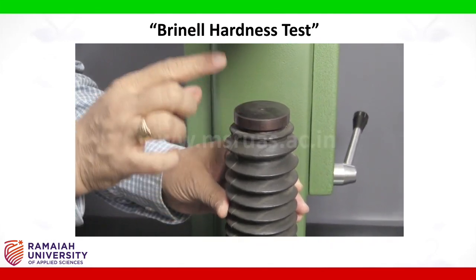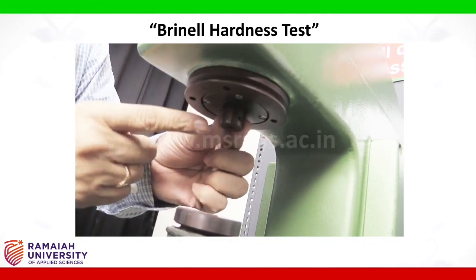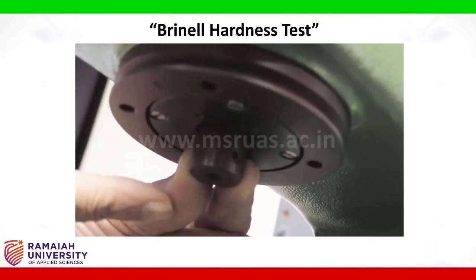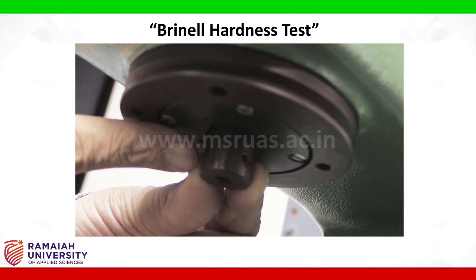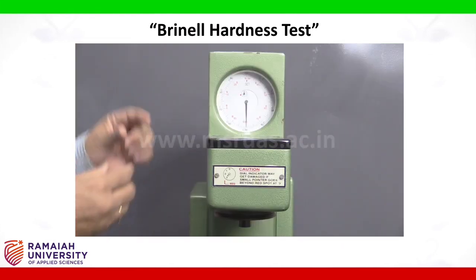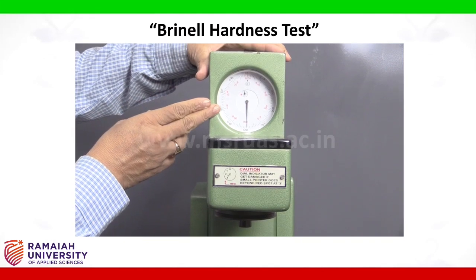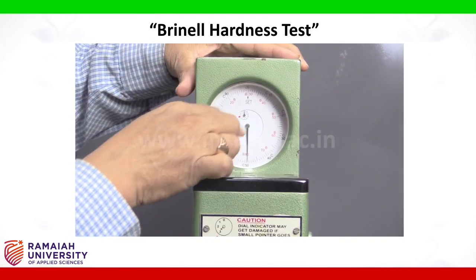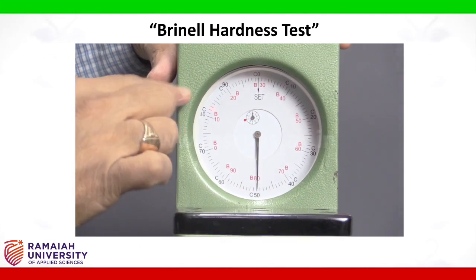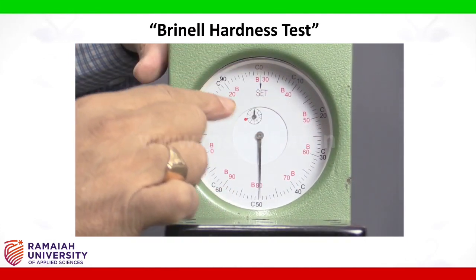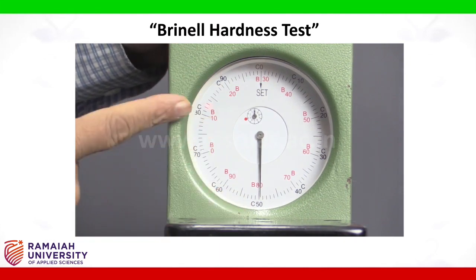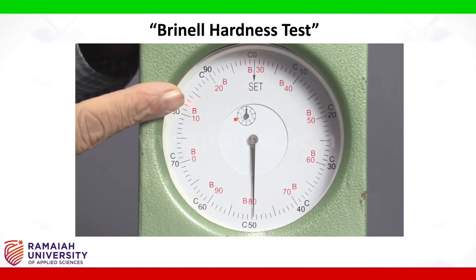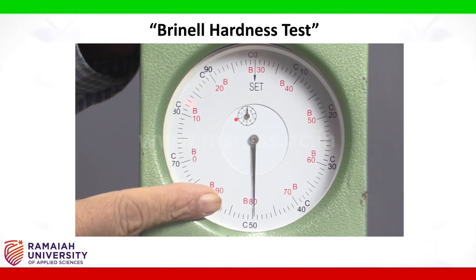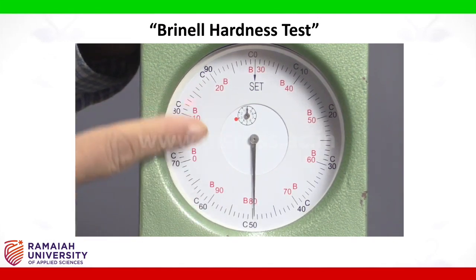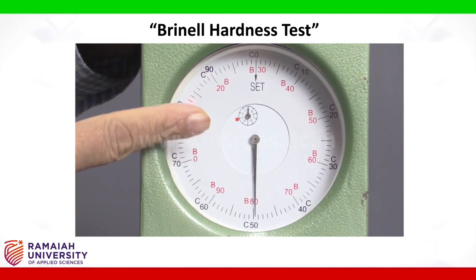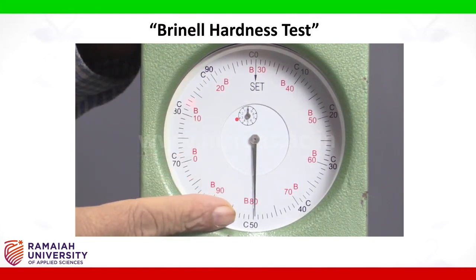On the working table we keep the specimen. The machine consists of the main shaft to which the indenter is fixed with the help of the Allen key. Next is the dial gauge. The dial gauge consists of an outer scale and an inner scale. The outer scale is the black C scale and the inner scale is the red B scale. In addition to the scales, there are two indicators here, one small and one big. For applying the minor load, both the indicators are used, and for the major load, the bigger indicator is used.